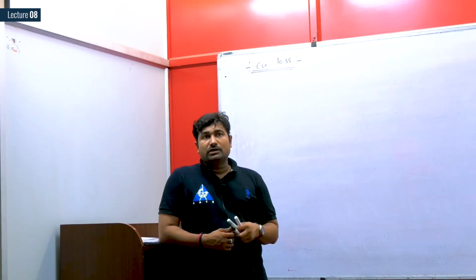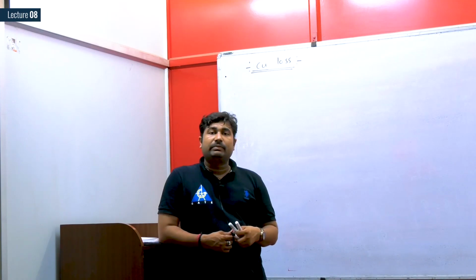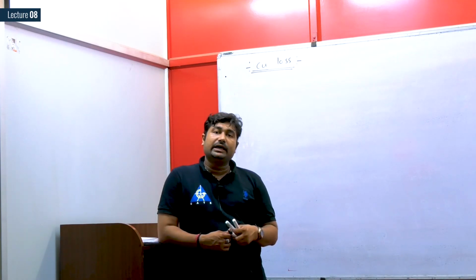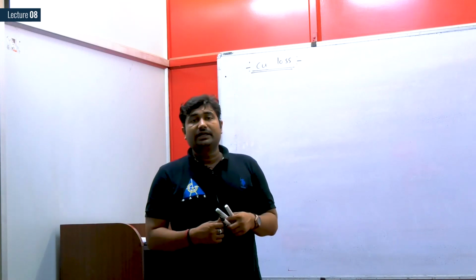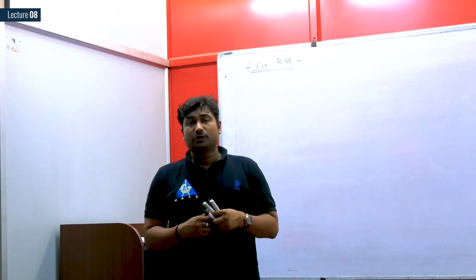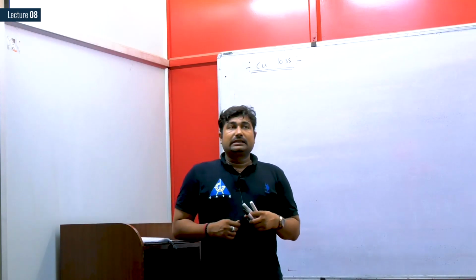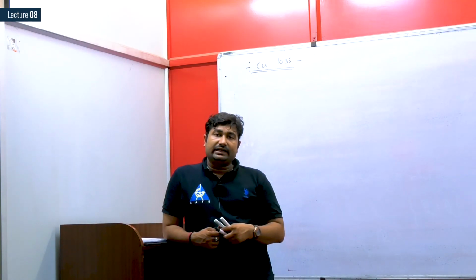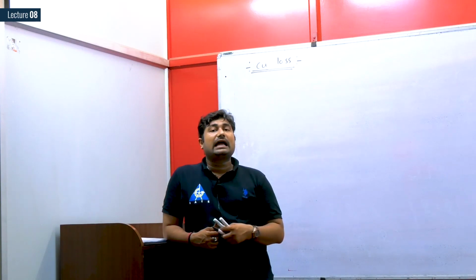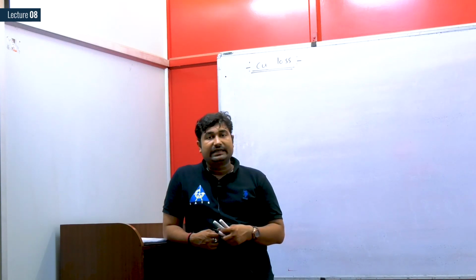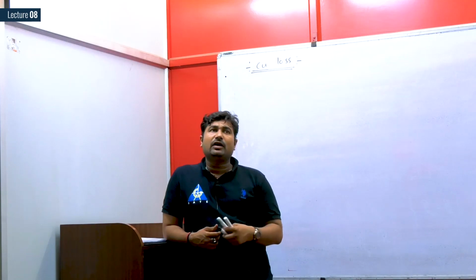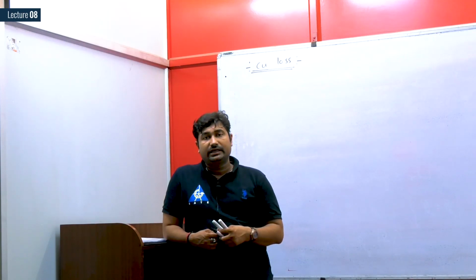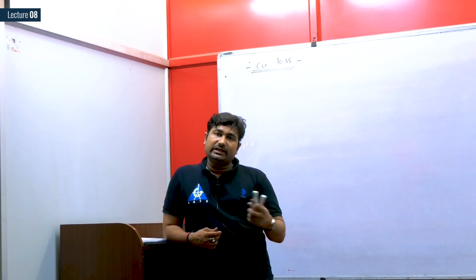So if the copper loss is mentioned on the nameplate in the format of R per unit, definitely that R per unit is under certain conditions. If the conditions change, your resistance is going to change. Since the standard operating temperature of electrical machines is 75 degrees centigrade, these losses are calculated at 75 degrees centigrade. However, we have a relation of the resistance of a conductor, that is copper conductor, with temperature.